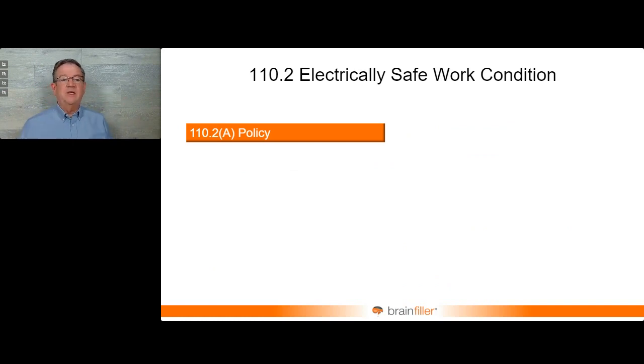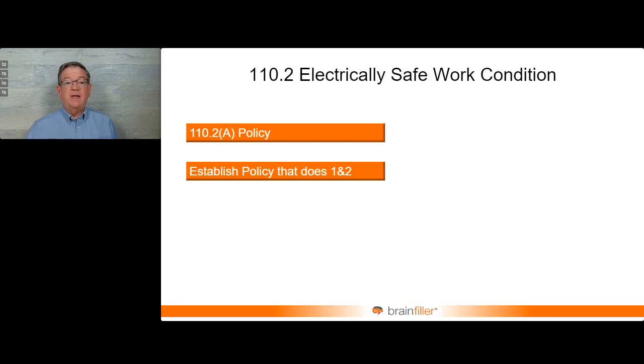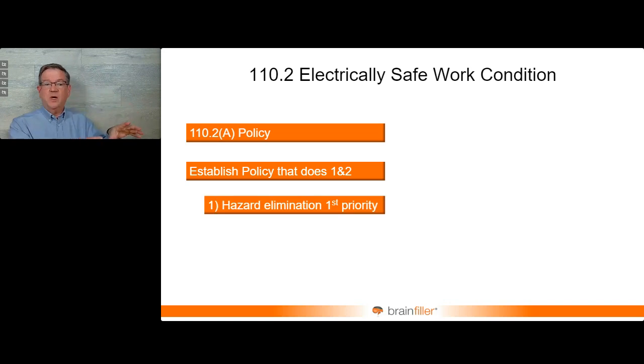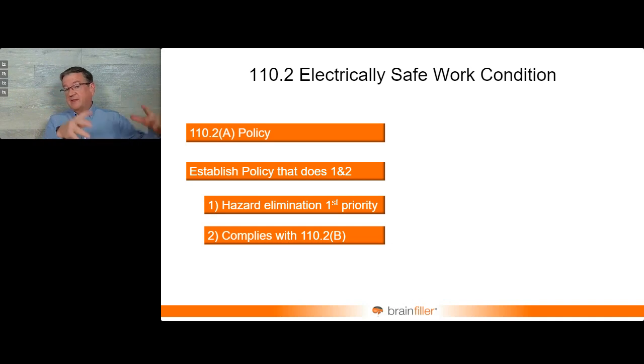A simply states you have to establish a policy that does items 1 and 2. Okay, what are those? Well, number 1, this is where the hazard elimination comes in. It's still ranking first. We had to have the scope, but once you get past the scope, hazard elimination is always the first priority. Eliminate the hazard. The second part of this is, okay, so you eliminate the hazard, then there's a reference that it's got to comply with what's in B, 110.2B. Well, okay, what's in 110.2B? Well, let's take a look.